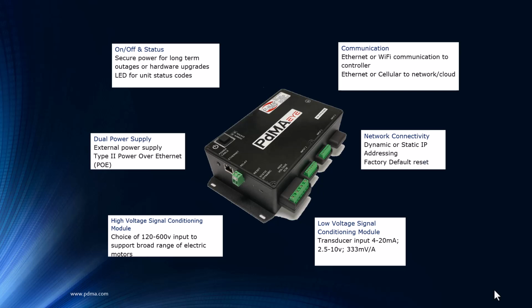Good point, not so much the CTs, but the voltage connection. You can definitely tap off the same voltage connections as the MTAP, but you'd need dedicated CTs for the PdMA EYE versus the MTAP2. Good point, if you were going to put in the MTAP, it's not necessary anymore. Right, if you were going to replace the MTAP, yeah, the same CTs would go. But again, what we've done now is raised the resolution and precision of the inrush startup.